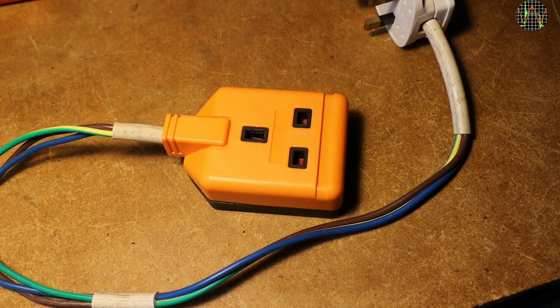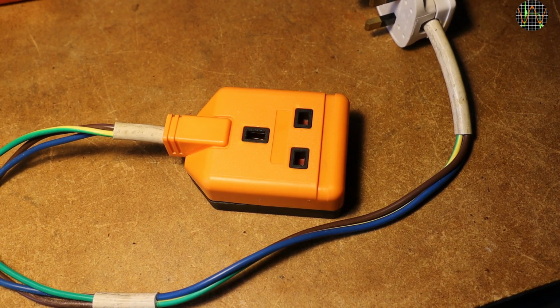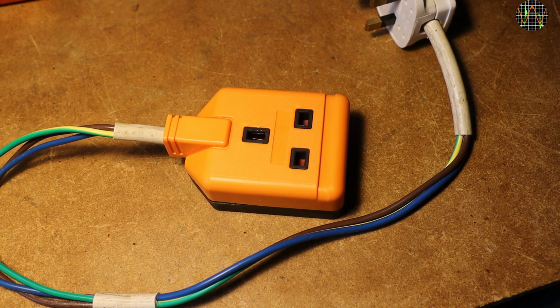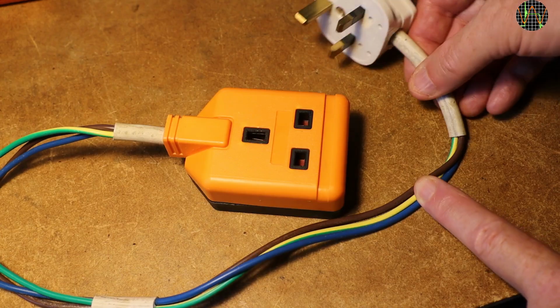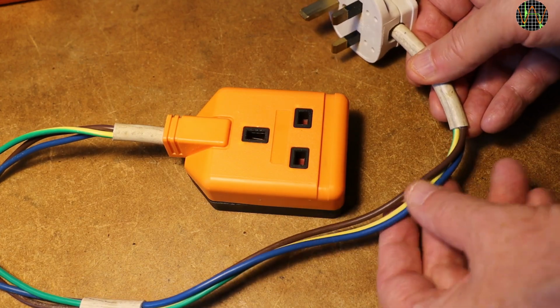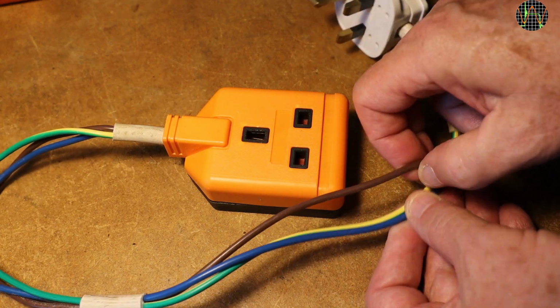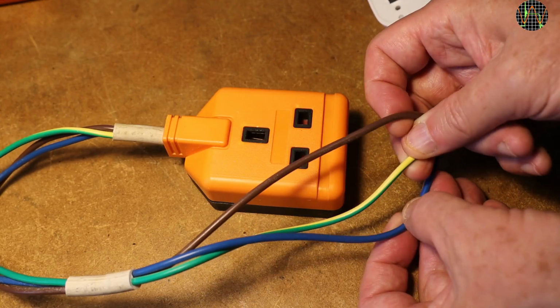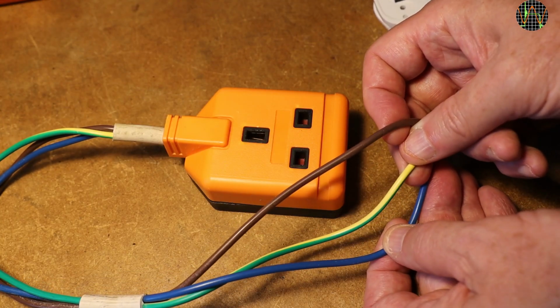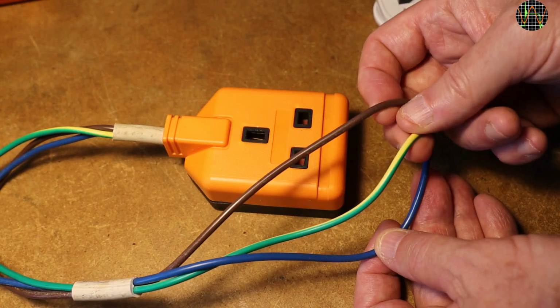Power sockets are pretty tight for clamp meters, and I made myself such an adapter, which is actually just a mini extension cable. I am using UK sockets and plugs, but you can easily construct something like it for the standards used at your location. There's nothing special here. The three conductors, live, which is the brown wire, neutral, which is blue, and earth, which is yellow-green, are connected straight from the plug to the socket.